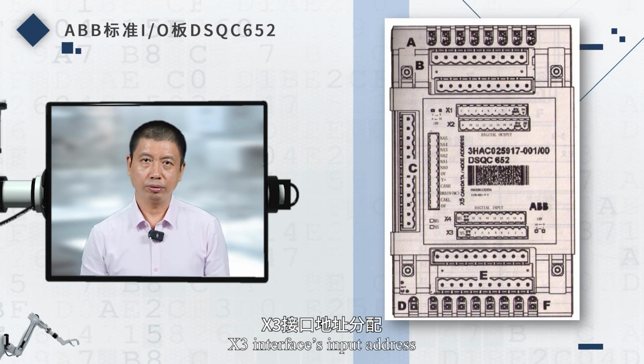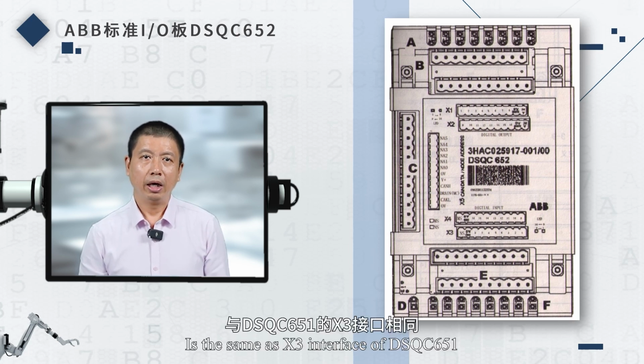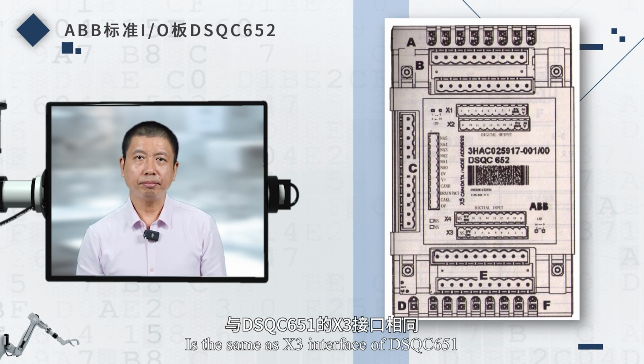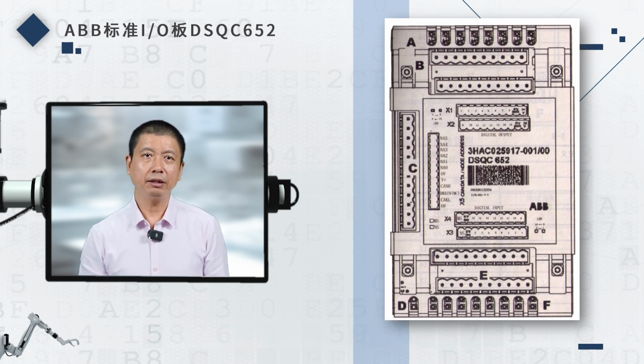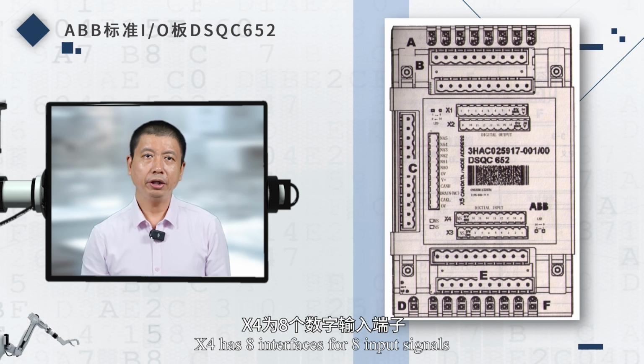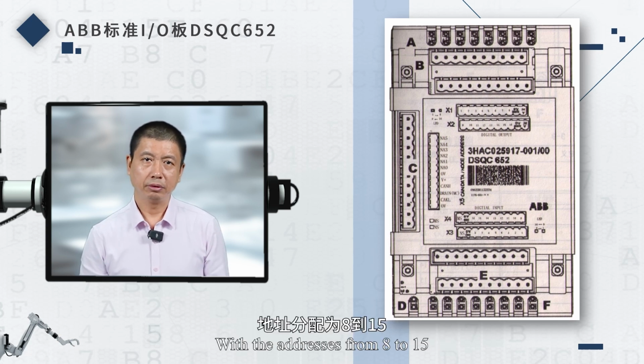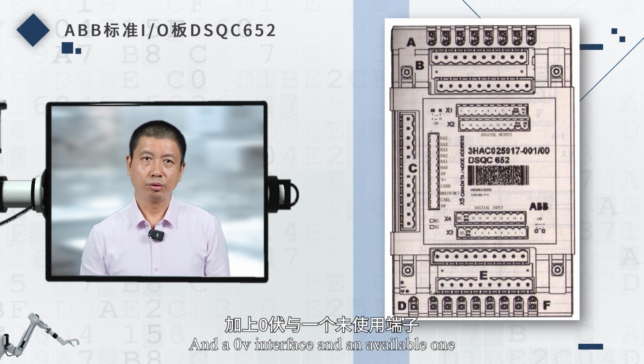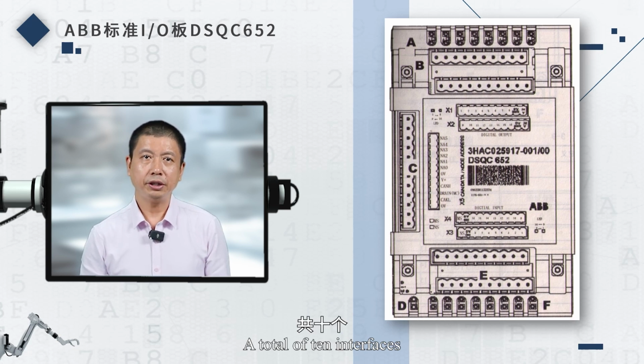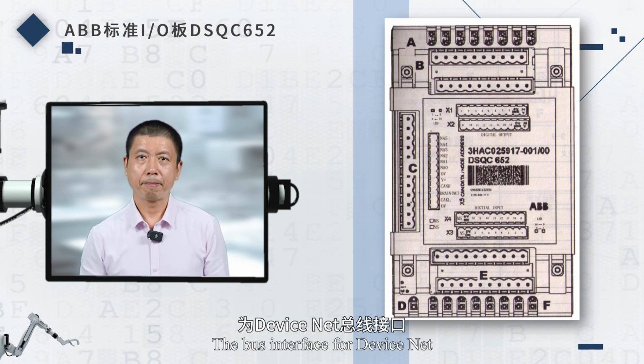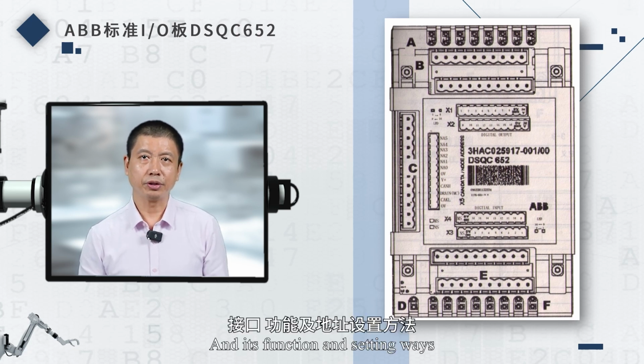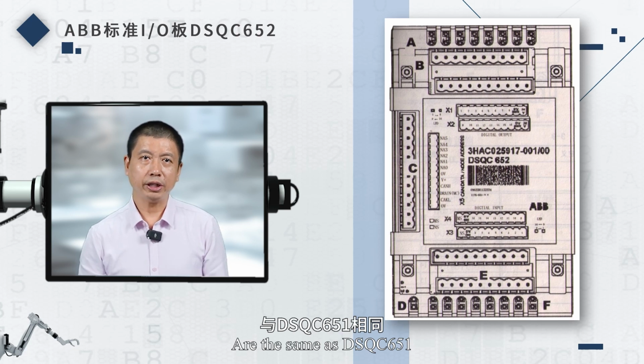X3 interface input address is the same as X3 interface of DSQC651. X4 has 8 interfaces for 8 input signals, with the addresses from 8 to 15, and a 0-volt interface and an available one, a total of 10 interfaces. X5 is the bus interface for DeviceNet, and its function and setting ways are the same as DSQC651.